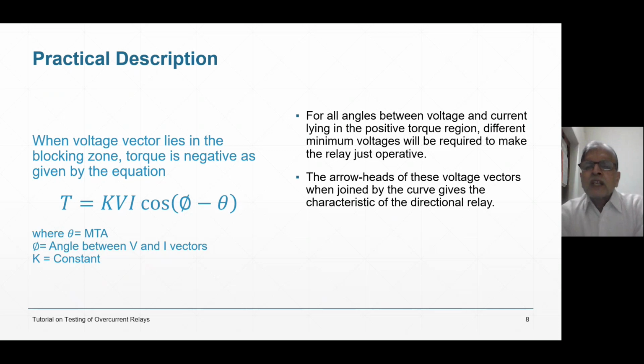For all angles between voltage and current, yes, at the maximum torque angle, I need minimum voltage. What is the meaning of maximum torque angle? If phi is 90 degrees and theta is 90 degrees, cos 0 is equal to 1. That means I will need minimum voltage at that time because cos is maximum. But when the angle differs, then I need a little more voltage, right? But some minimum voltage I need. What is that minimum voltage? That minimum voltage is different from relay to relay.